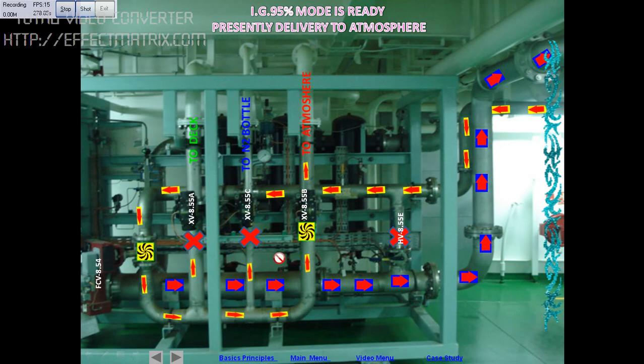In this picture you can see these are the filters here, and this one is the heater. Normally the air is heated to 50 degrees before it is going to the membrane. Otherwise, if the temperature is 65, it will give an alarm and a trip.